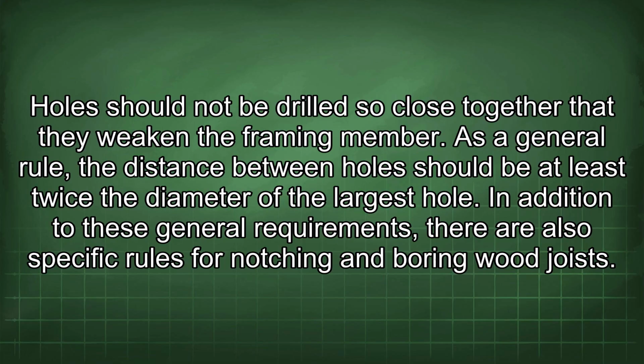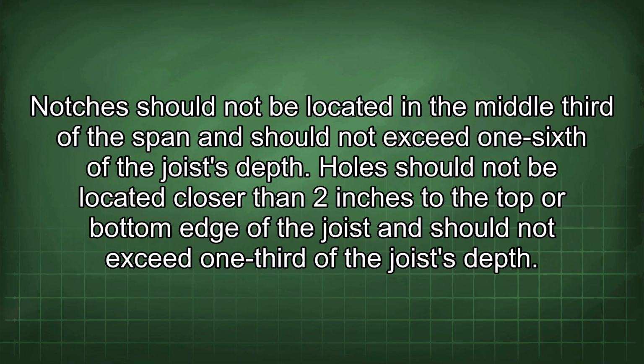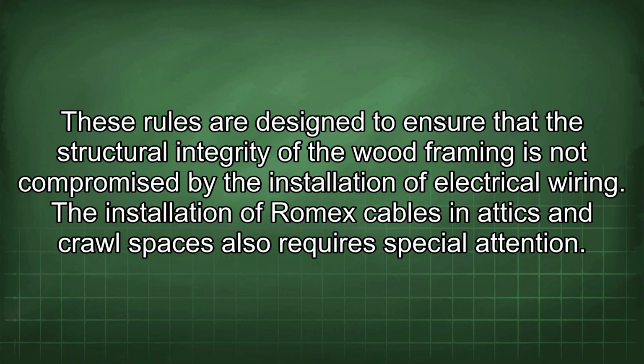In addition to these general requirements, there are also specific rules for notching and boring wood joists. Notches should not be located in the middle third of the span and should not exceed 1/6 of the joist depth. Holes should not be located closer than 2 inches to the top or bottom edge of the joist and should not exceed 1/3 of the joist depth. These rules are designed to ensure that the structural integrity of the wood framing is not compromised by the installation of electrical wiring. The installation of Romex cables in attics and crawl spaces also requires special attention.